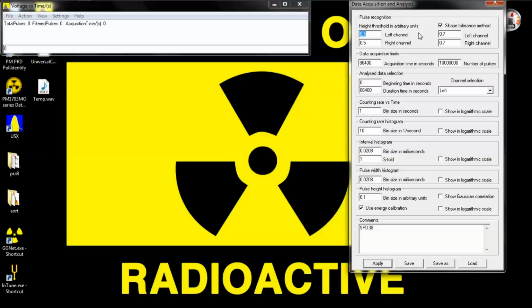Now, basically these settings have a lot to do with the pulse shape. Because if you remember when the pulse shape came through, it looked kind of like a heart monitor when they look at somebody's heart. And the pulses will come through slightly different shapes, and what you're going to try to do is tell the computer, how true do you want to be? Do you want to be absolutely only accepting pulses that are perfectly shaped right? Or do you want to be really lax and allow any old looking pulse to be measured? Because you're going to get background interference and all kinds of deformed looking pulses that come in.